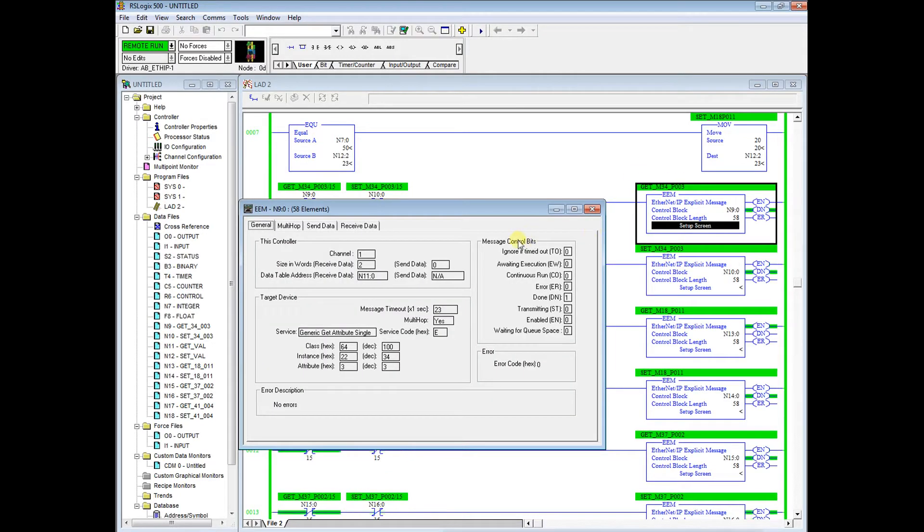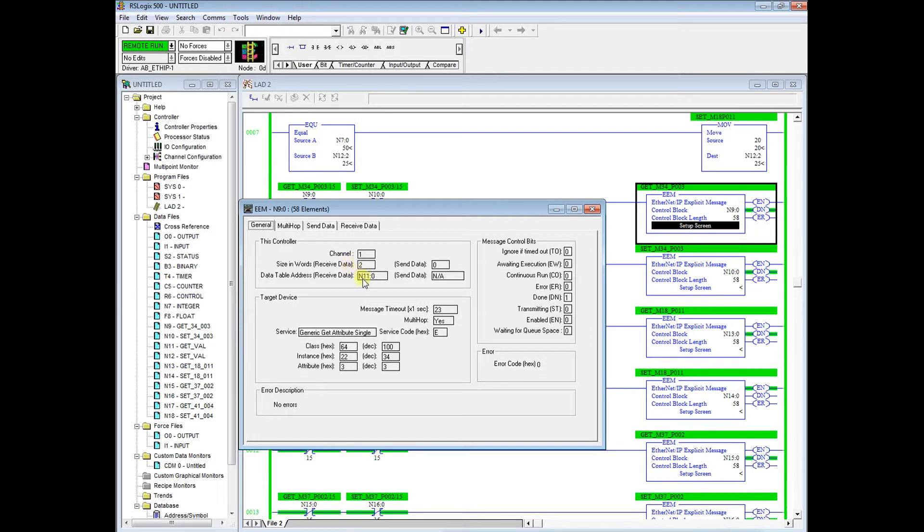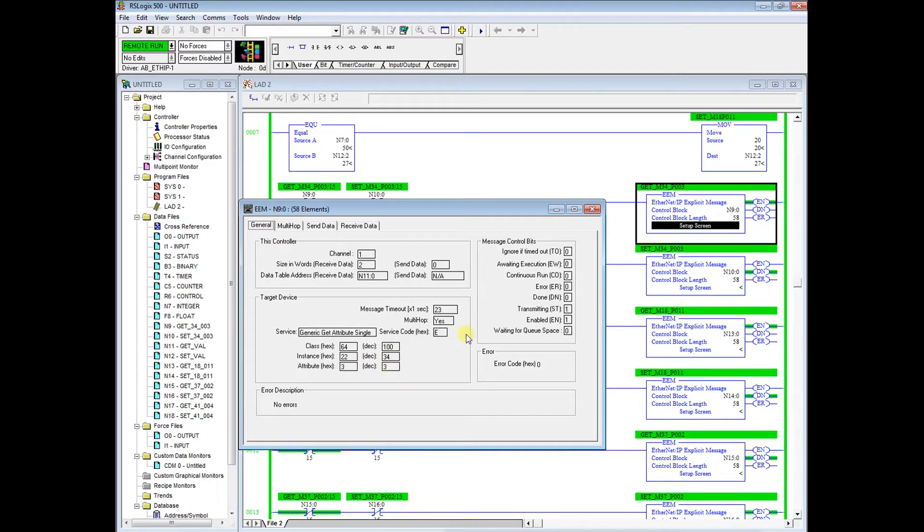If we double click here we can see where we will be storing. So get, we will go out to the drive, get it, and then we will store it in a location. We're going to store it into integer file 11:0, so it'll be two words. And down here we can see where we have it set up for menu 34 parameter 3.